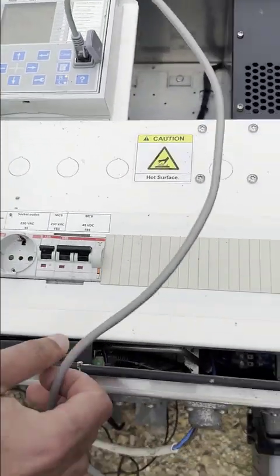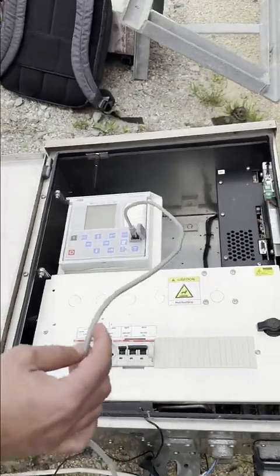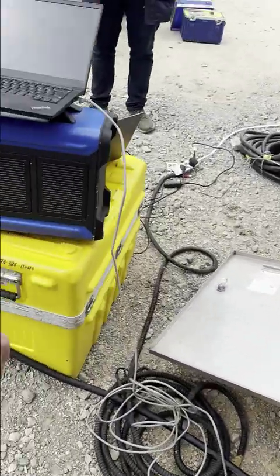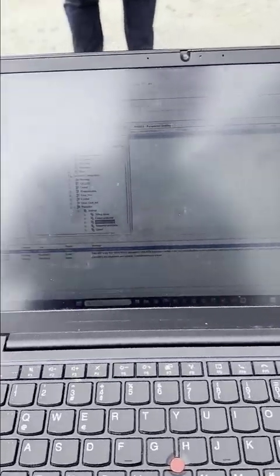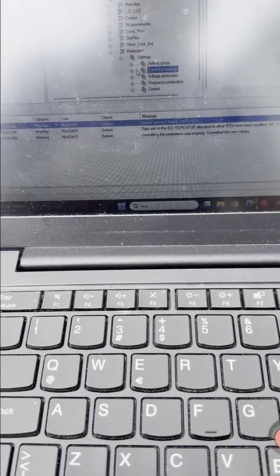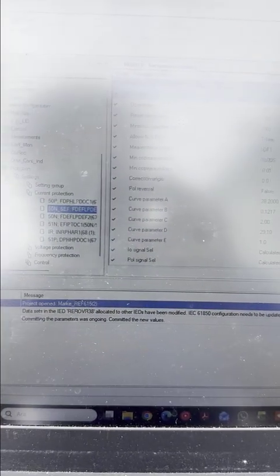Then here is the Ethernet connection to be connected with the PC for the PCM600 software to see the parameter setting. As you can see from here, okay, so here is the BCM. Here is our software connected to the REF615. You can see the current protection, for example. So here is the first stage of the earth fault, which is a definite time 50N, as you can see from here. And you can see also the parameter setting.